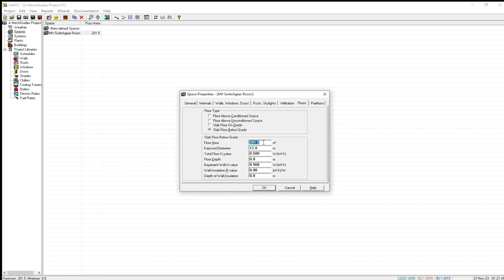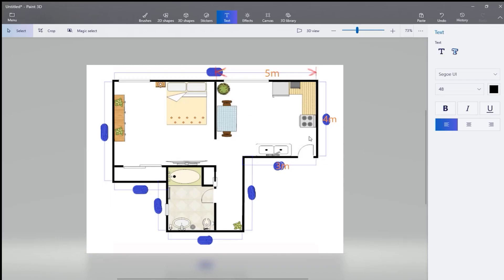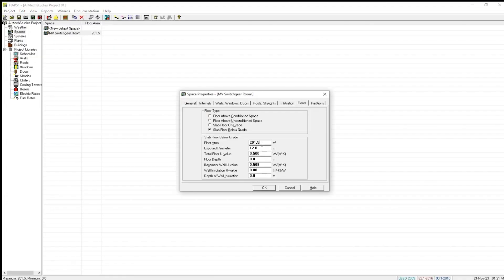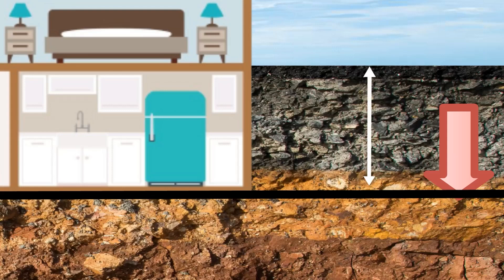Now let us understand slab floor below grade. This is an example only. Let us consider this is below grade and the dimensions are the same. The floor area will be 5 multiplied by 4, equal to 20 square meters. The exposed perimeter is also the same, 12 meters. The total floor U-value will be the same as already discussed. For floor depth, let us consider 3 meters.